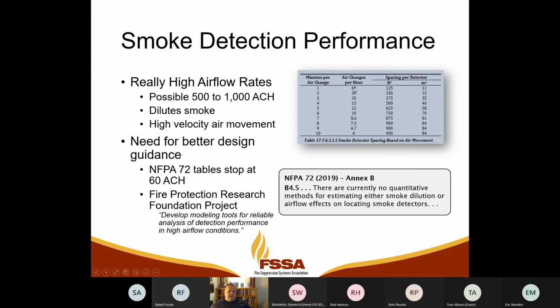So the maximum that this chart goes to is 60 air changes per hour, and says to use 125 square foot spacing. So you take the square root of 125, and some of you are probably better at head math than me. I think that's like 11 feet and some change. So in a normal 2-foot ceiling tile grid, we usually space detectors at 10-foot spacing, and that's pretty darn tight.